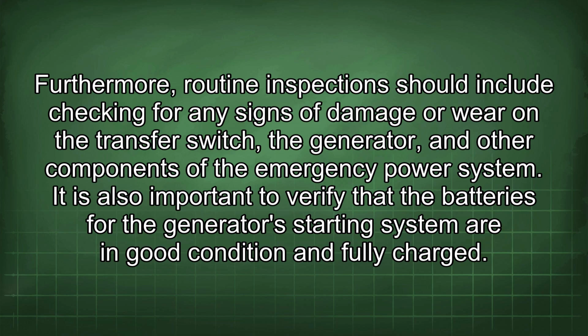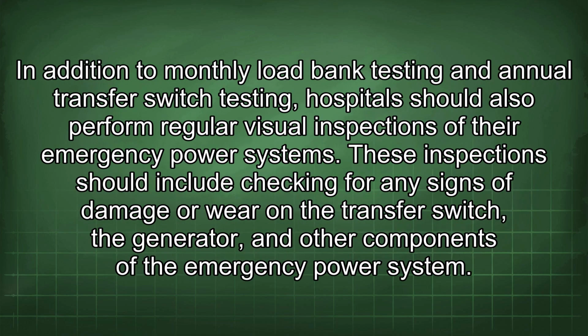It is also important to verify that the batteries for the generator's starting system are in good condition and fully charged. In addition to monthly load bank testing and annual transfer switch testing, hospitals should also perform regular visual inspections of their emergency power systems.